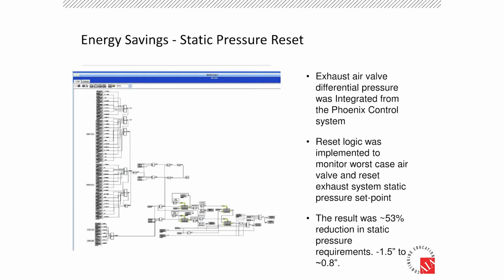This involved replacement of a few air handlers, about 2,000 office terminal boxes, and about 2,200 laboratory terminal boxes. So again, you start thinking about what those data points mean - all the flows, flow set points, trends, temperatures, all those different points being integrated back to a system. One of the first things we did, this was a Phoenix control system, and anyone familiar with the hardware knows they don't truly read airflow.